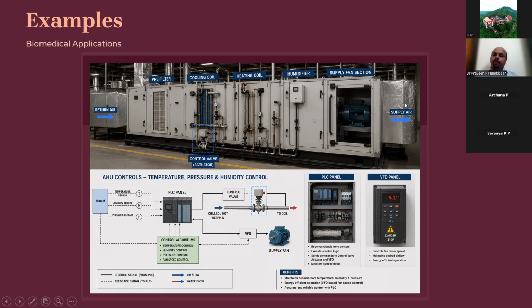This is the supply duct, supply air. It goes to the room. If I reduce the supply air to the room, and you can see at the left-hand side the return air, which comes from the room, I increase the return air speed by using a blower motor. This is the blower motor. I will increase the return air and reduce the supply air. What will happen? The pressure will go down inside the room, correct? And in the corridor, I'll do the opposite. So that is how the blower motor functions.